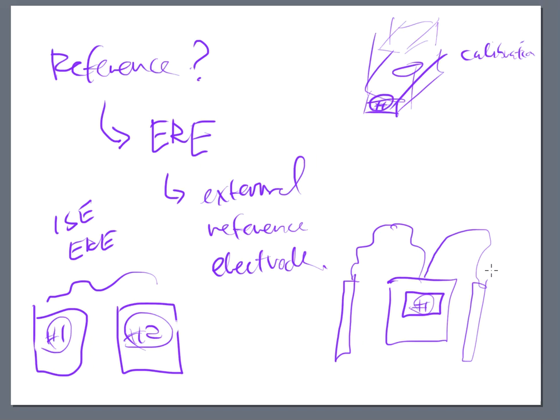We had to keep the two chambers separate from each other. We had two containers that we were using in a laboratory. One of the probes would be dipped down into my sample, and this is what I would read. The other probe would be dipped down into some type of reference solution. So I'm going to call this a blank solution, even though it really wasn't blank, there was stuff in there. But it gave me a reference point, and that's why we called it the external reference electrode.